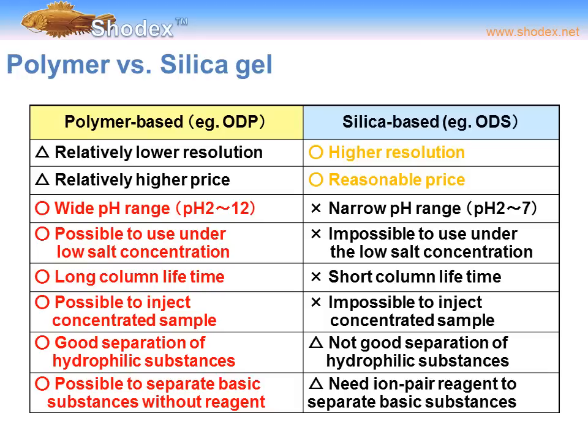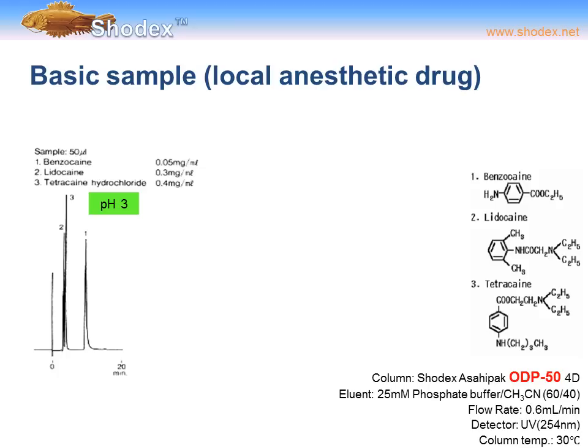With all the choices of HPLC columns available today, there are still only two basic choices: a polymer-based ODP column or a silica-based ODS column. A polymer-based ODP column has relatively lower resolution and higher price; however, it can operate at a wider pH range of 2 to 12, it's possible to operate under low salt concentrations, it has a longer column life, it allows injection of concentrated samples, provides good separation of hydrophilic substances, and can separate basic substances without a reagent.